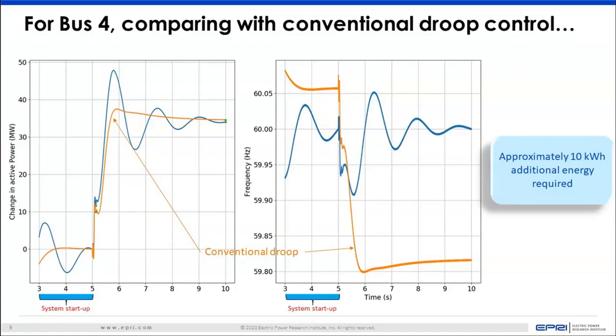So the difference in the frequency response is easily observable. The Droop frequency response reflects our traditional kind of response, where it settles at an off-nominal value, which is around 59.8 hertz in this scenario, but our constant frequency control based on distributed slack bus is able to bring the frequency back to 60 hertz very fast. And if you observe the active power response for these two scenarios, the trend looks very, very similar.